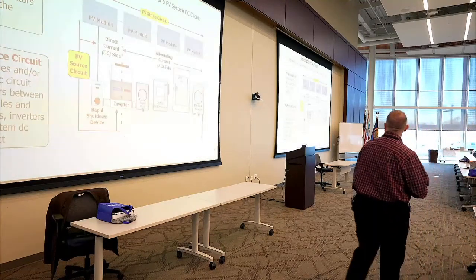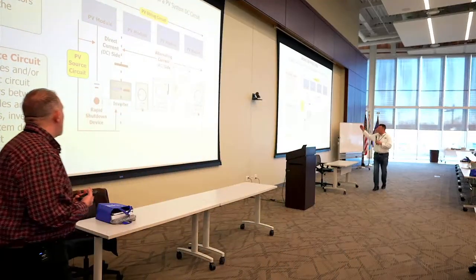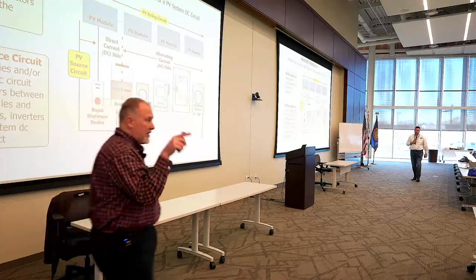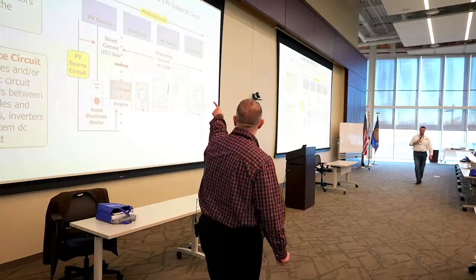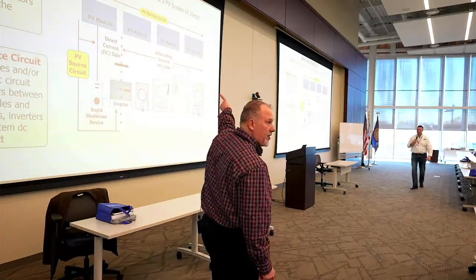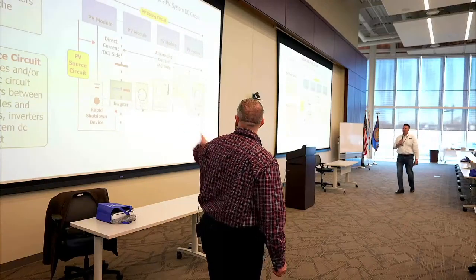Clarity—the illustrations help. What's the difference between a PV string circuit and a PV source circuit? The illustration shows you the location. The string circuit is between the modules. The PV source circuit is between the modules and the shutdown or the inverter. So definitions with PV systems have come a long way, very helpful, and you have to understand where you're at in the system to know whether you're following the requirements for a PV string circuit or for your PV source circuits.